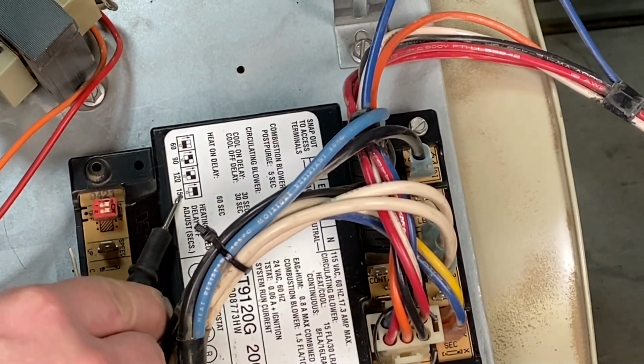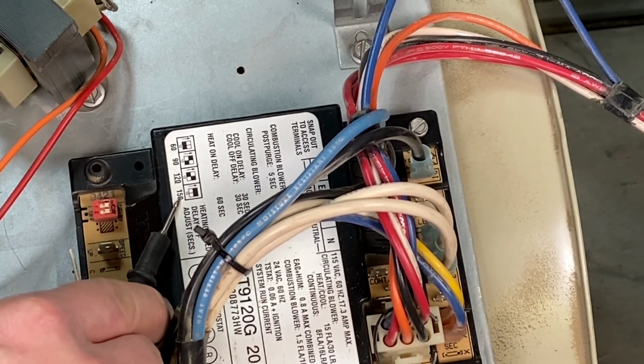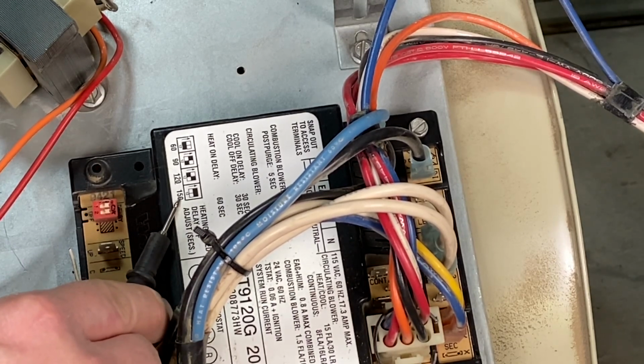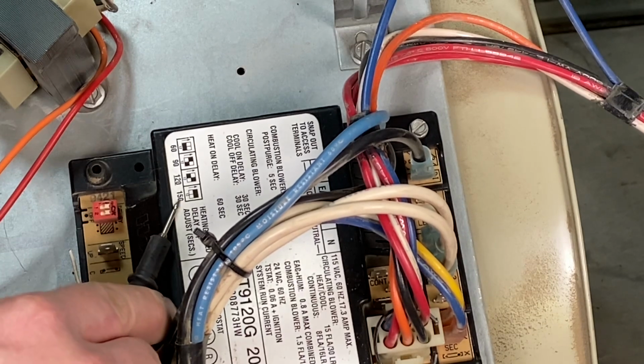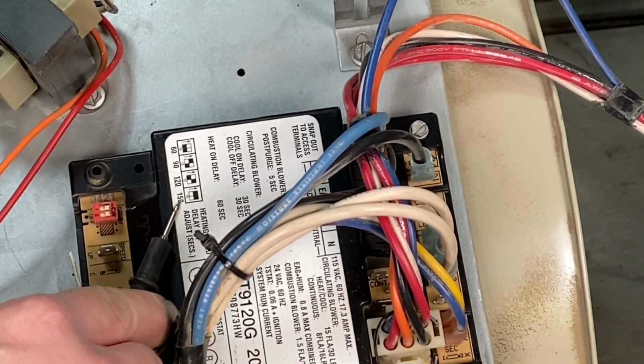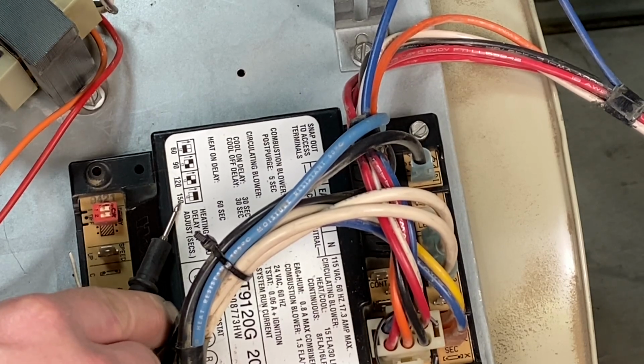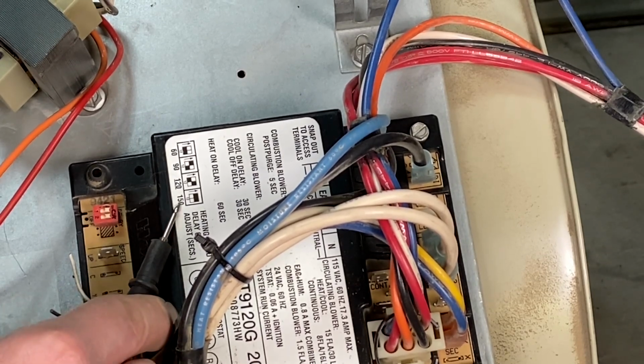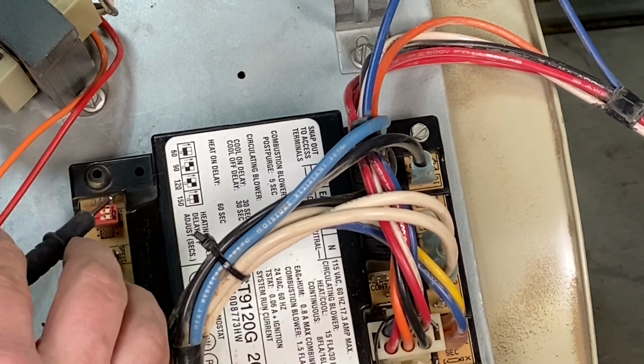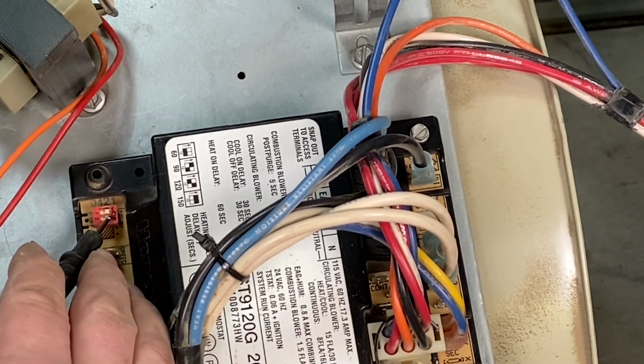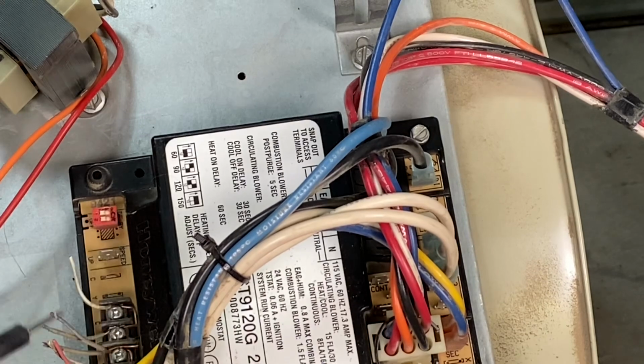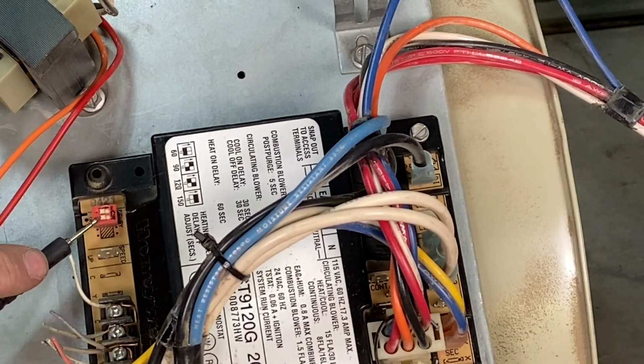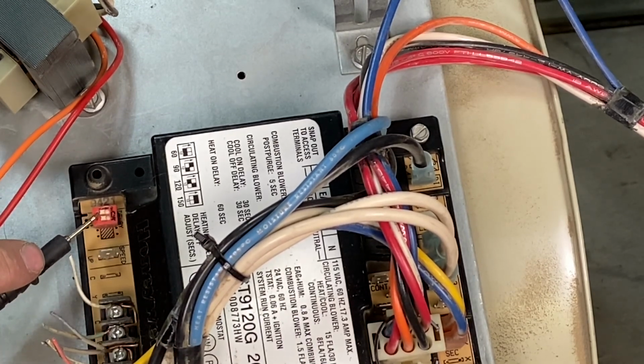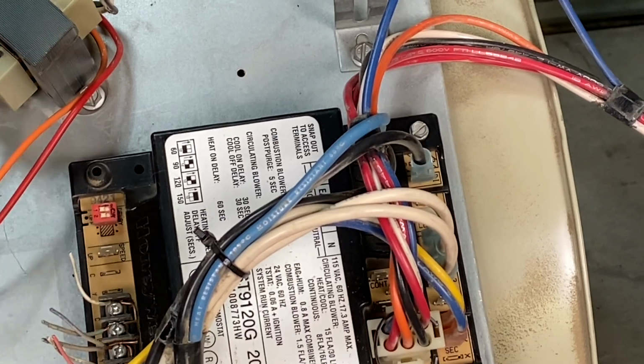So this would make it more efficient. I'm getting every little bit of heat out of that heat exchanger that I put into it with the gas. The problem with the 150-second off delay is it's going to be pretty close to room temperature air. And room temperature air moving is going to feel cooler. So the customers would complain, hey, it feels like it's blowing cold air. That's why they give you these adjustments that you can change the off delay. In this case, a 60-second off delay, there's still a lot of heat left in the heat exchanger, but also warm air is still blowing out.